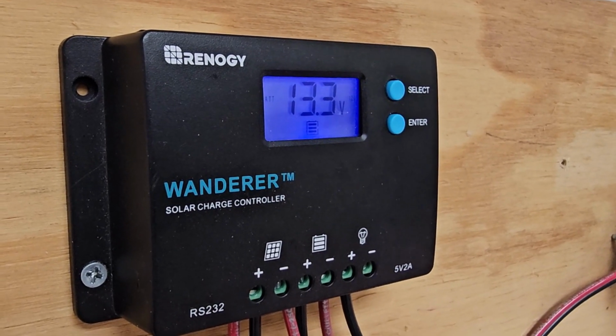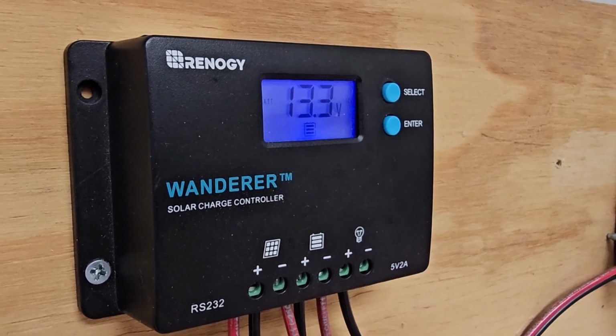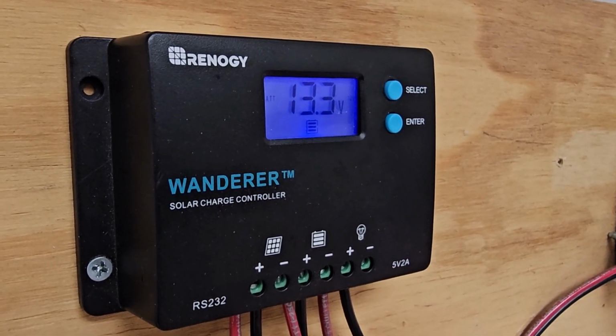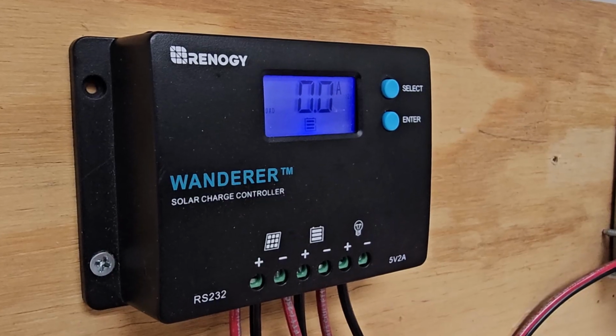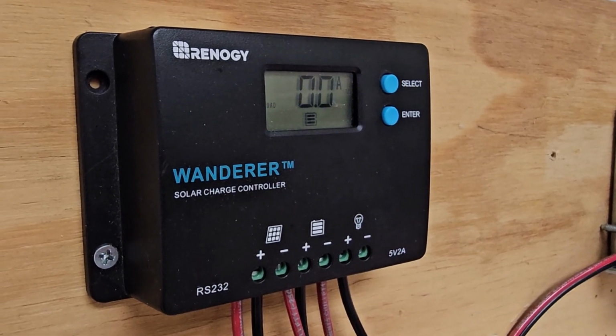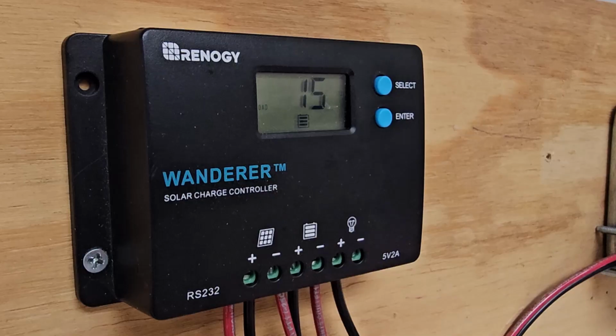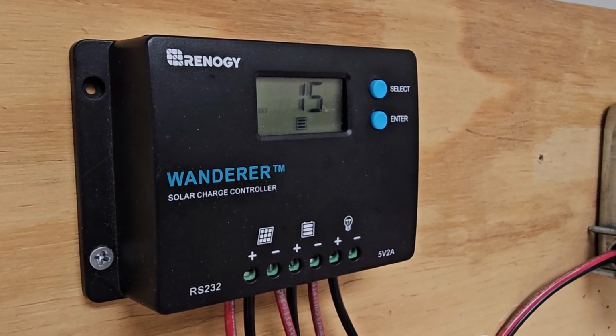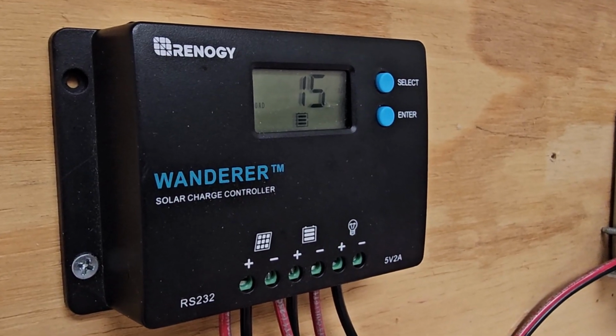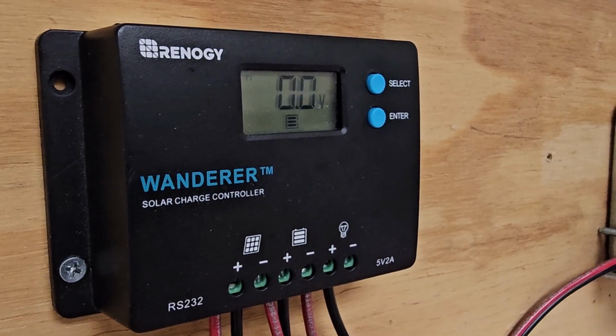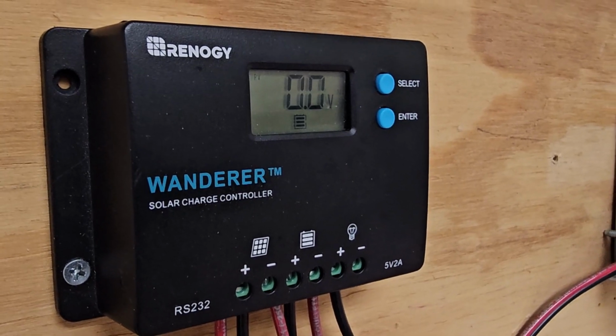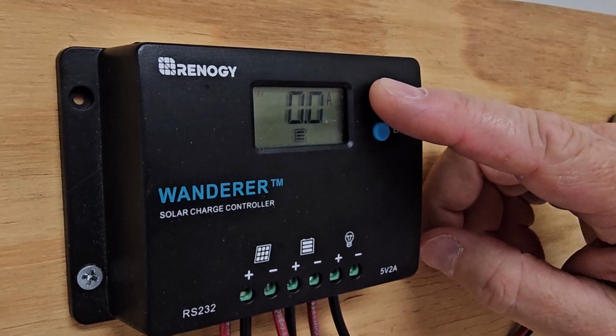Now we'll program the mode of operation for the load. The charge controller has load settings that can turn on the load after dark or turn off the load a specific number of hours after the PV module stops supplying power. We want to set the charge controller to keep the load on all the time.